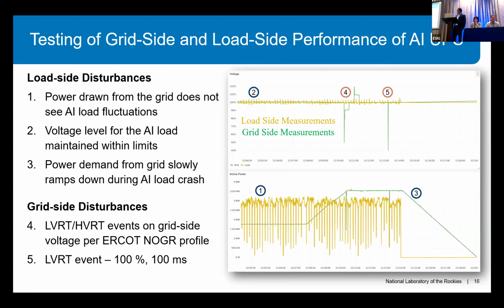The second load disturbance is here, where the load suddenly goes to basically zero. So it's an AI load crash. That can happen because of some failure in the equipment. It can also happen if all these data centers are operating on a synchronized algorithm. If the algorithm crashes, the demand can also crash. Again, the grid side power doesn't crash at the same instant, but the grid power is ramped down in a manner such that the grid doesn't see this big disturbance.